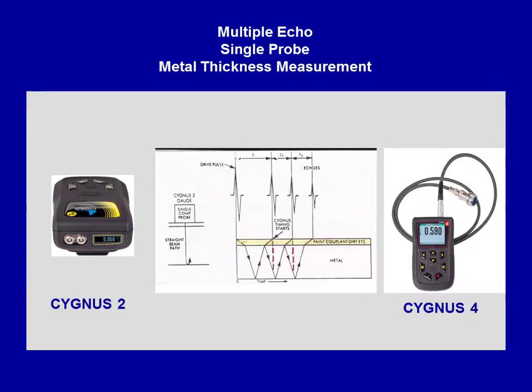So the issue always, when doing thickness testing, is what is the shape or the angle of the two walls that you're trying to put sound into, and what happens to the sound when it strikes the other wall? Well, if it's being deflected away from the transducer, where's it going? The sound never came back to you. If, like you say, you had pitting on the other side, and it ricochets and bounces around before it makes its way back to the transducer, what's the chance of getting three echoes to follow that same path? Slim to none.